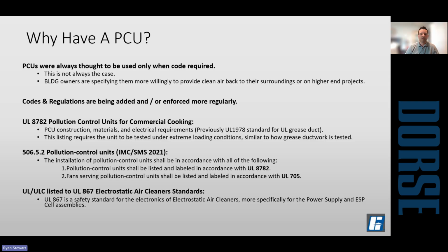Over the past few years, they've actually developed standards specific to pollution control units. UL 8782 is specific to PCU construction, materials, and electrical. Previously, they just tested the units to the UL 1978 standard, which was for UL grease duct, and really all they were looking at was the cabinet construction. The new listing requirements look at the unit tested under extreme loading conditions, which is what you're going to have from grease buildup.